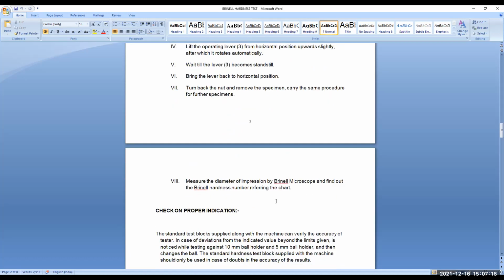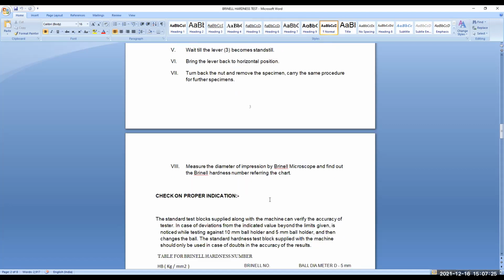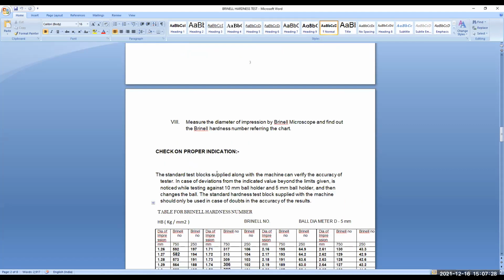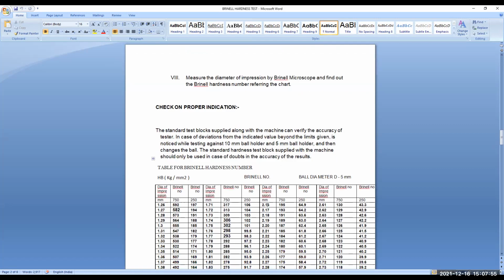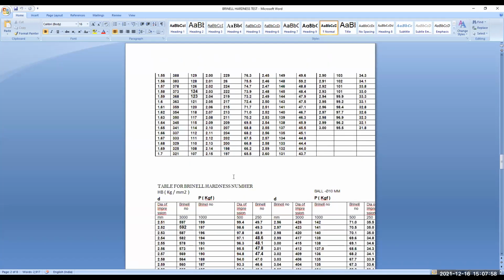The diameter of the impression is to be checked by the Brinell microscope, and find out the Brinell hardness number by referring to the chart. The test blocks supplied along with the machine can verify the accuracy of the tester. Some of the test blocks are given here. In case of variation of the indicated value beyond the limits given, check the ball holder again, and if needed, change the ball. The standard hardness test blocks supplied with the machine should only be used in case of doubt about the accuracy of the result. Now the Brinell hardness numbers are given.